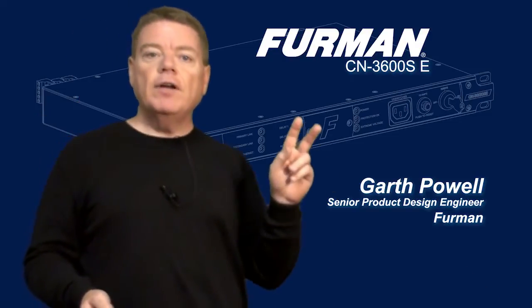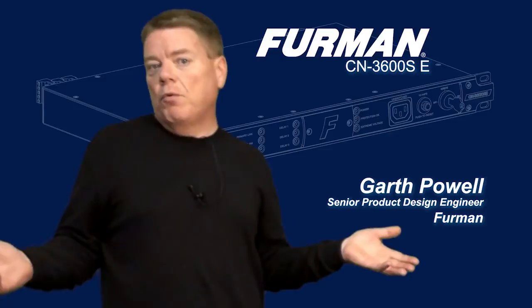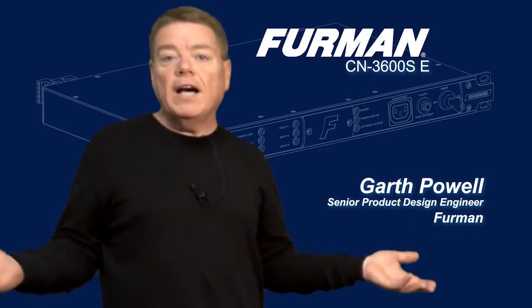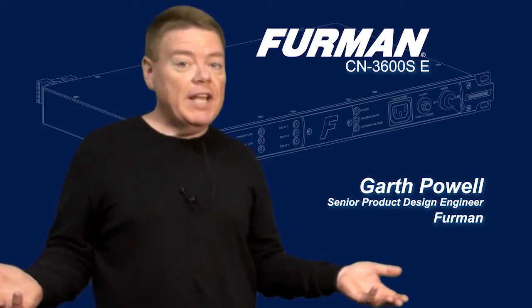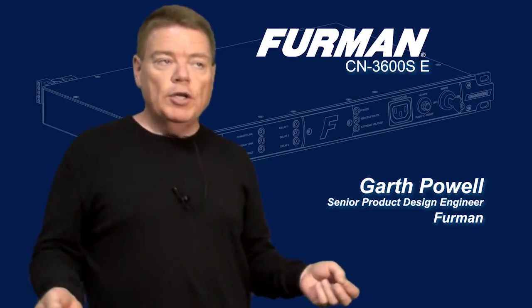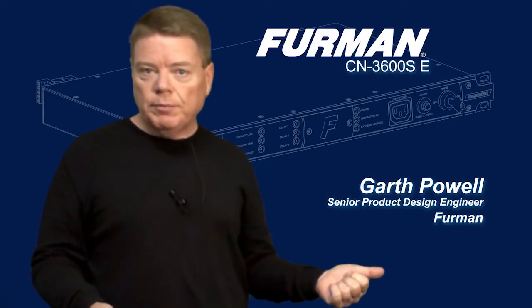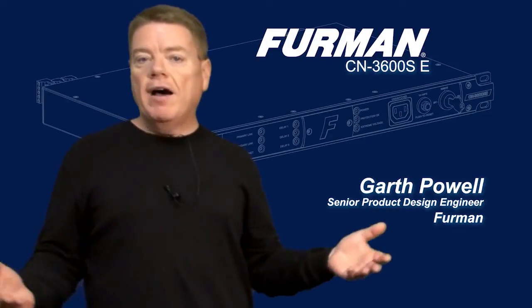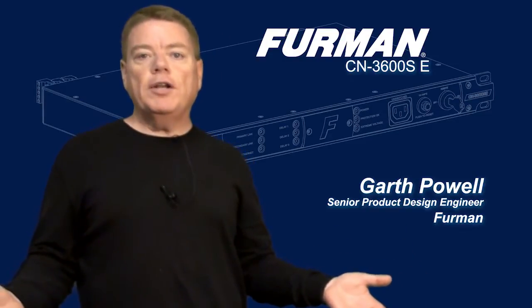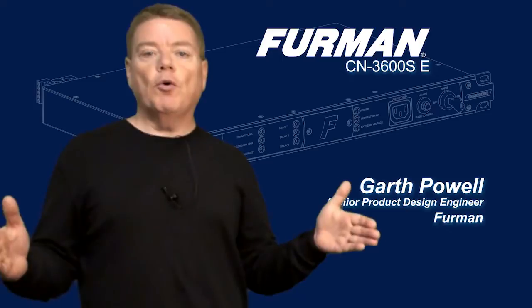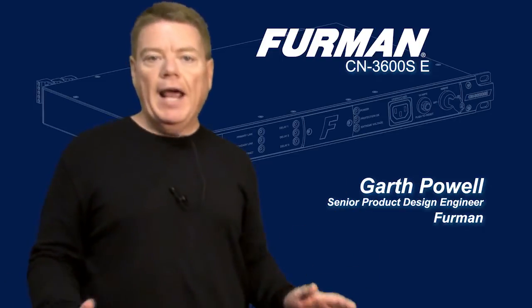And if you have anywhere from 3 to 4 to 5 to many dozen amplifiers turning on potentially at the same time, you're going to take out your wall circuit breaker, you're going to take out your local circuit breakers, and if you have a generator, its governor will darn near want to freeze on you. We can't have this, so we have to stagger their operation.